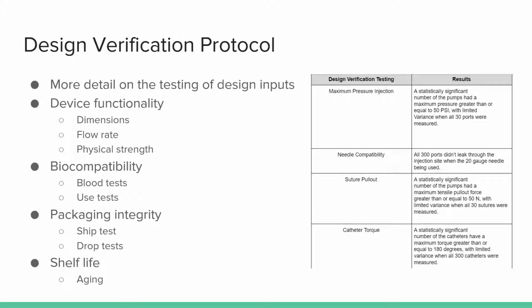The verification plan has similar content to the master validation plan, but with an emphasis on the verification testing. The devices are assessed primarily for device functionality with these tests, but some tests assess biocompatibility, packaging integrity, shelf life, and key design parameters, which are covered in more detail in the specific test plans.